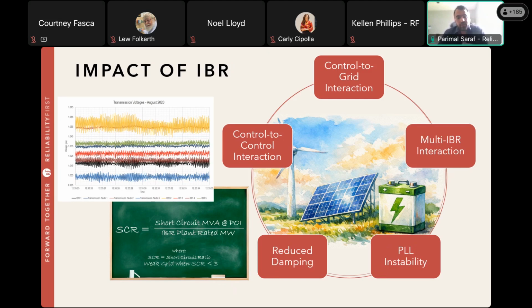And reduced damping I already talked about. This is predominantly a function of inertia getting replaced in the system, and that results in reduced damping of these oscillations. And there's a snapshot on the left that is an example from AEMO in Australia. Basically, what happened in this particular event is that under weak grid conditions, the PLL of grid following IBRs installed in that region demonstrated instability, and that resulted in oscillatory behavior. Multiple IBRs in that general region all started oscillating, and that's how these oscillations were observed in the transmission level voltages in that region in Australia.